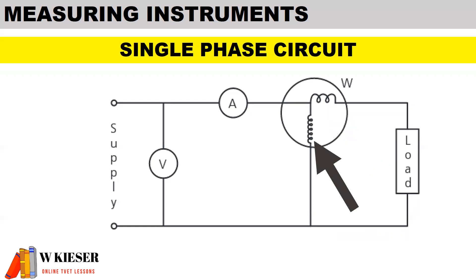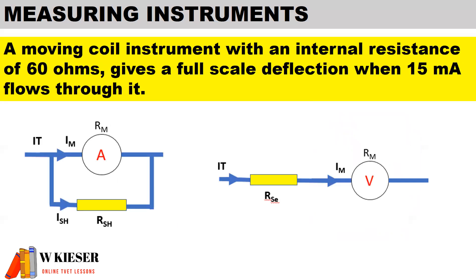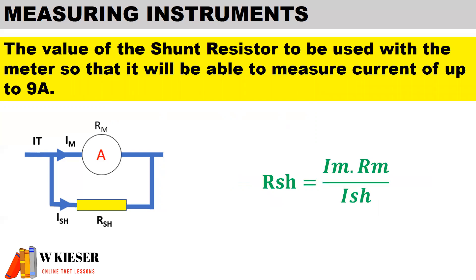For our moving coil instrument calculation — also known as a galvanometer — a moving coil instrument with an internal resistance of 60 ohms gives a full-scale deflection when 15 milliamps flows through it. This instrument can be used to either measure current (represented as an ammeter) or measure voltage (represented as a voltmeter). The objective is to determine the value of the shunt resistor so that the meter can measure current of up to 9 amps.